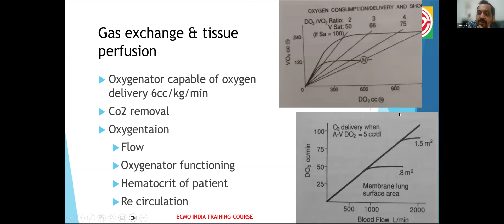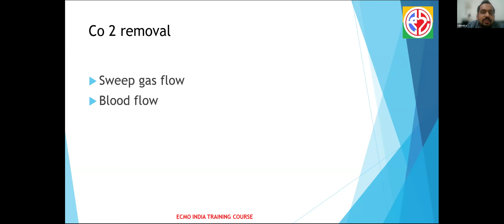Coming to carbon dioxide removal, it mainly depends upon your sweep gas flow and the blood flow. Once you initiate the ECMO, the ratio of blood flow to sweep gas flow should be 1:1. The maximum you can go up to is 1:2. That means if the blood flow is around 5 liters, the maximum sweep gas flow you're going to keep will be around 10 liters for any ECMO patient. More than that, the sweep gas flow is not going to remove more carbon dioxide from the system.